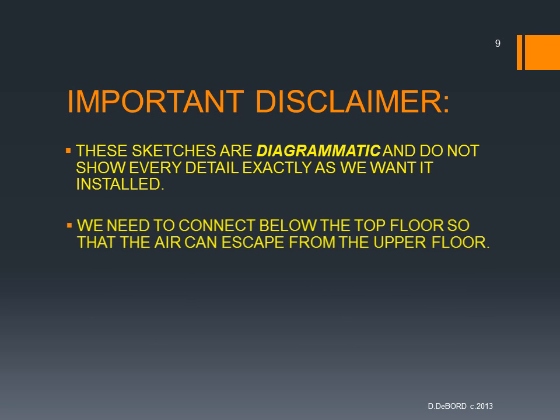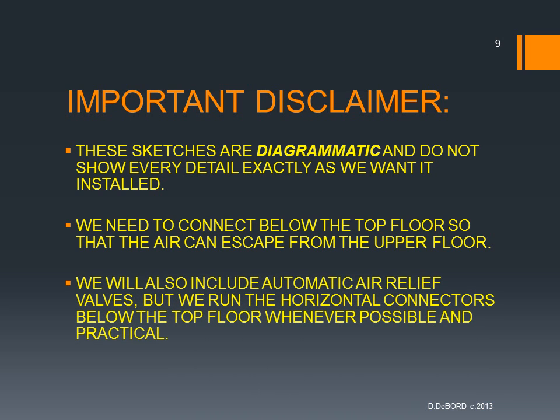It's important to remember that these sketches are diagrammatic, much like most of the work that we do. We always have notes: do not take the dimensions off of these plans. We need to connect below the top floor so that the air can escape from the upper floor. We will always include automatic air relief valves, but we run the horizontal connectors below the top floor whenever possible and practical, just for that added security of knowing that when those fixtures are used at the top, the air comes out. It can solve problems in the future.